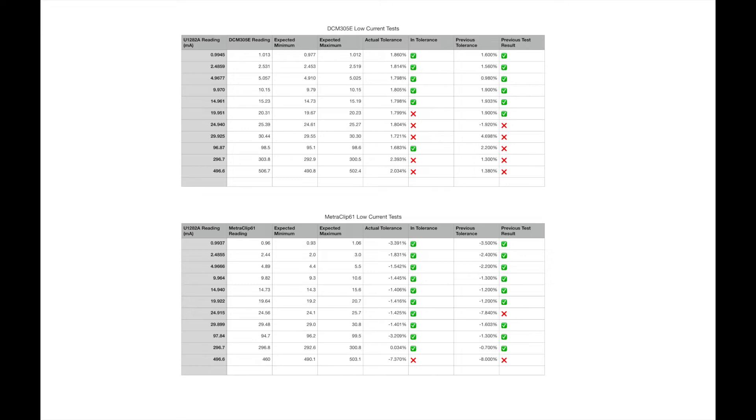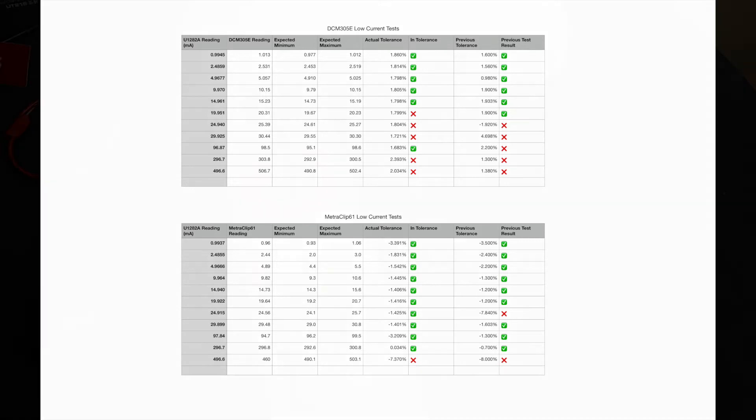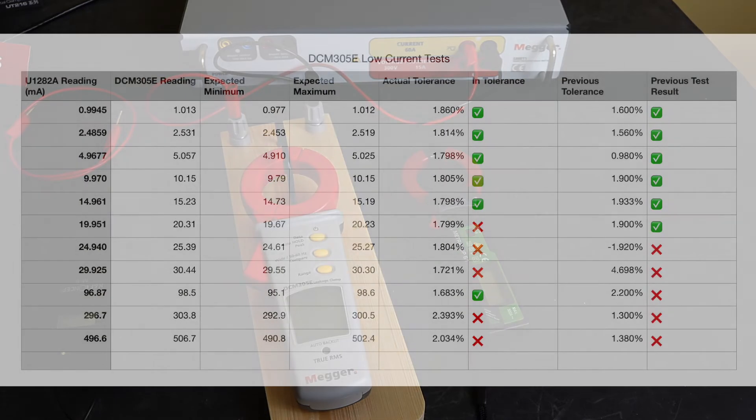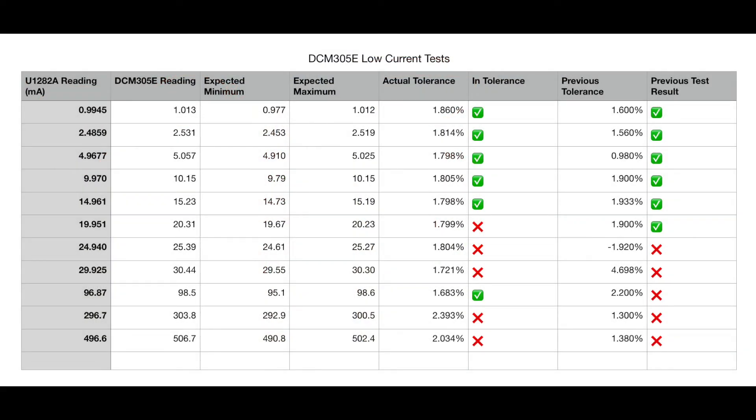Previous test result shows the measurements I made in the last video. Looking at the DCM305E more closely, you can see the actual result, overall result is pretty much similar. I've got five readings that are out of tolerance. The difference this time around is that the 100 milliamp I've now got in tolerance, but I got an out of tolerance reading on the 20 milliamp reading.